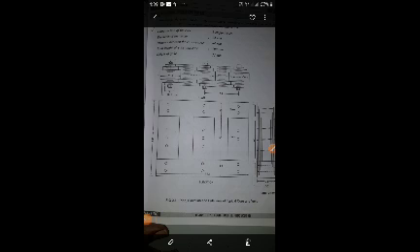Okay, transformer details also. Draw the plan, elevation, and end view of a 3-phase transformer core and yoke as shown in the figure. Draw the same to scale and make the dimensions. The cross section of the core is 3-stepped. Here the 3-stepped is given.